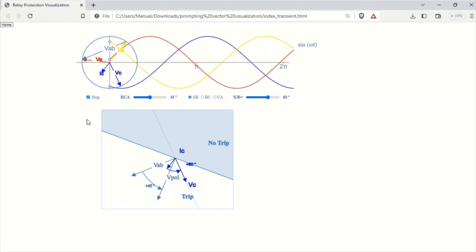I have a rotating vector representing the phase current IC and the phase-to-phase voltage VAB between phases A and B. I've also introduced a polarizing voltage, which is VAB shifted by an angle internally set in the relay.